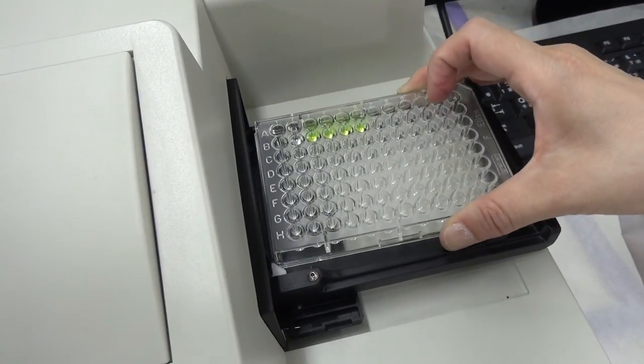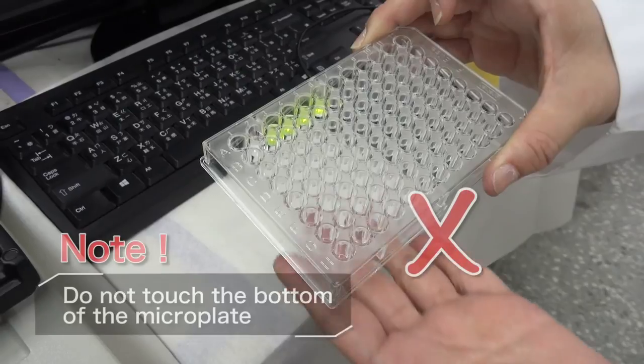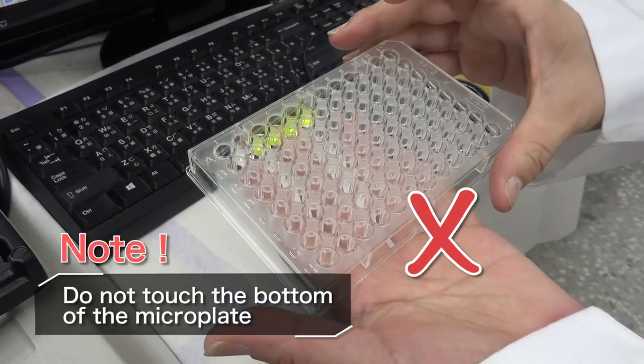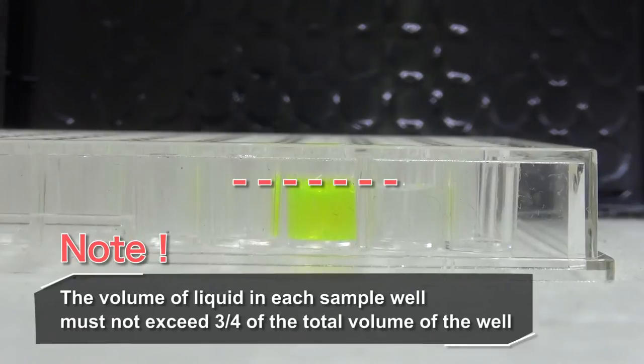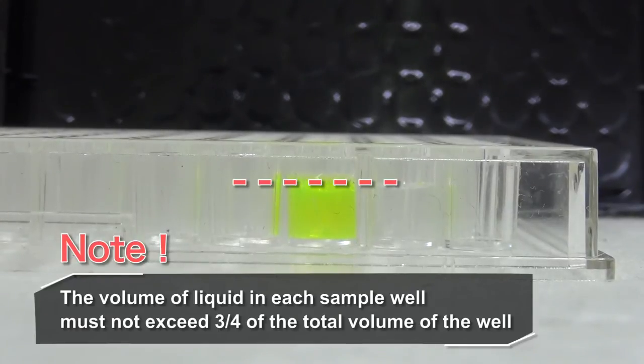4. Insert a microplate containing the samples. Do not touch the bottom of the microplate. The volume of liquid in each sample well must not exceed three-fourths of the total volume of the well.